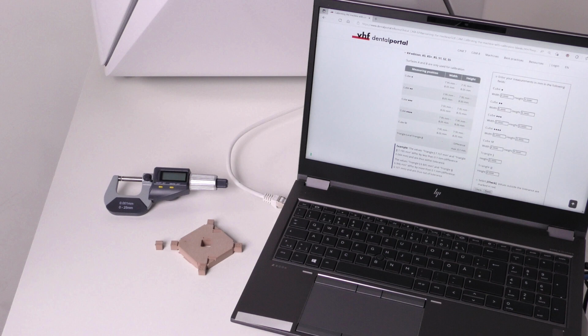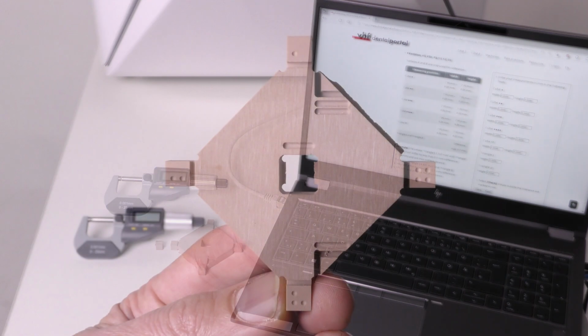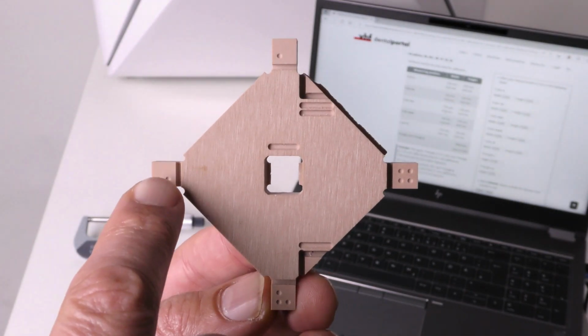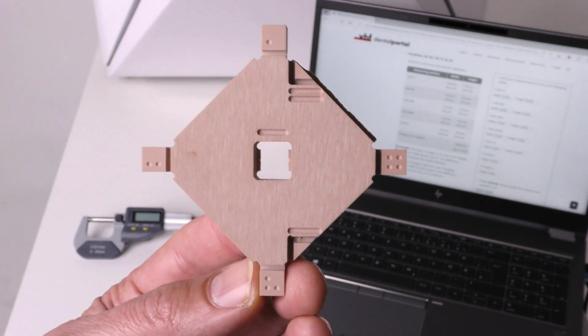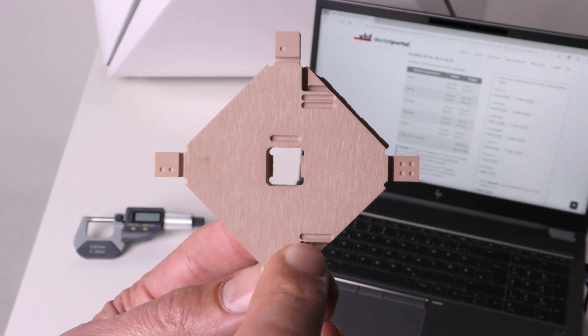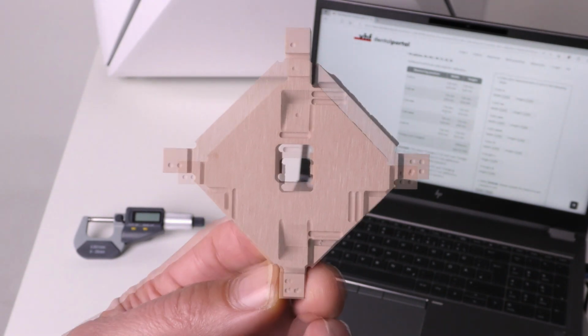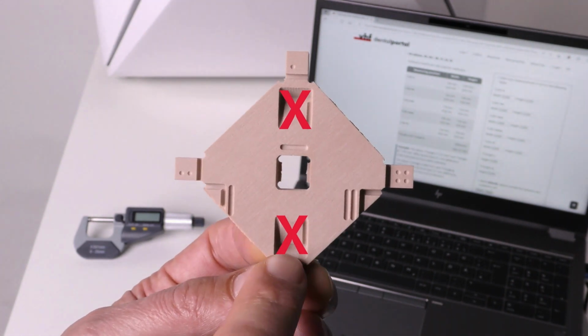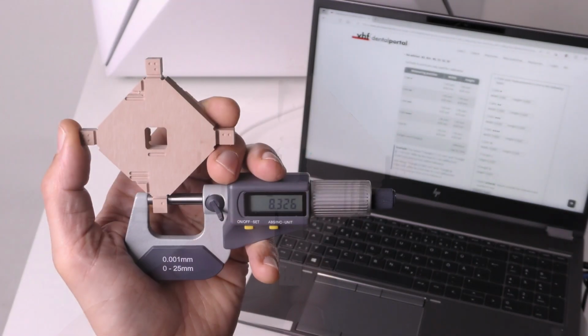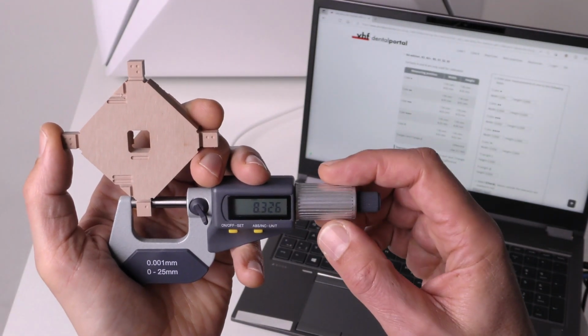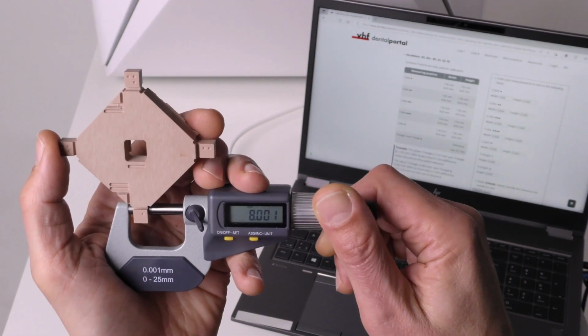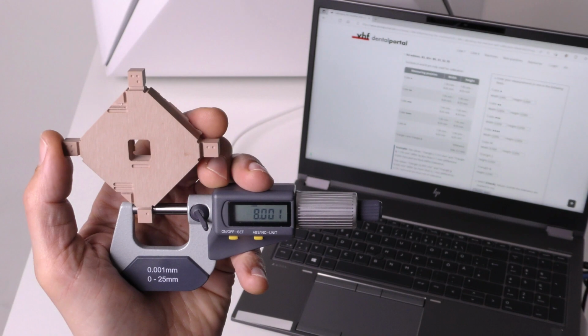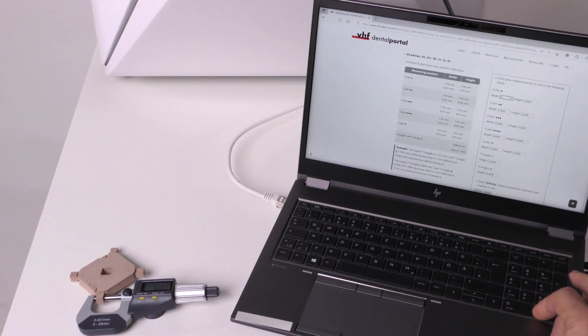The test specimen for the S series, K5, K5 Plus, E5 and R5 use 2 symbols to mark measuring points. Circles and bars. If your test specimen has slanted surfaces, you can ignore them for this task. Start measuring the width of the outer cube, which is labeled with 1 circle. Measure each point at least twice to make sure that the measured values are correct. Enter the measured value into the corresponding check table input field.